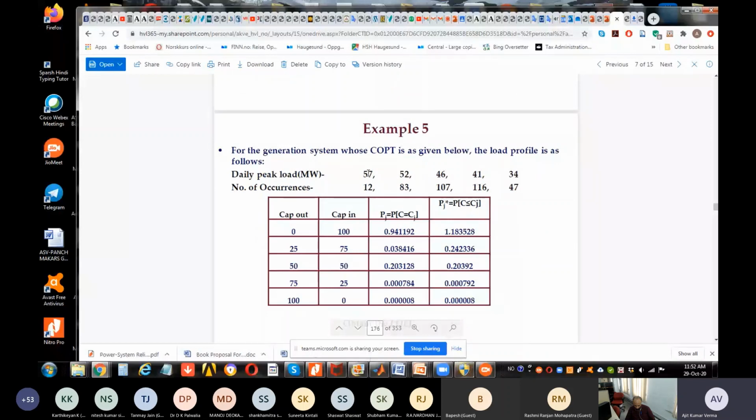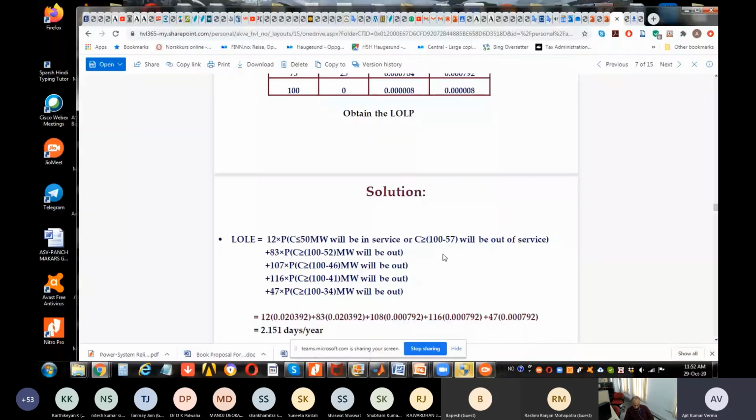12 occurrences of 57 megawatt. So when do you have loss of load? When the capacity is less than 75, so these three possibilities will cause loss of load.